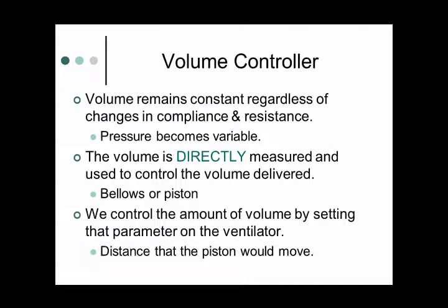Okay, volume controller. Volume controller means that the volume remains constant regardless of changes in compliance, and pressure becomes a variable that will change. So as compliance falls, volume stays the same, but the pressure would end up going up because it's a stiffer lung. Now this is unique in the sense that when we talk about a volume controller, we're really talking about something where the volume is directly measured as it's being delivered.